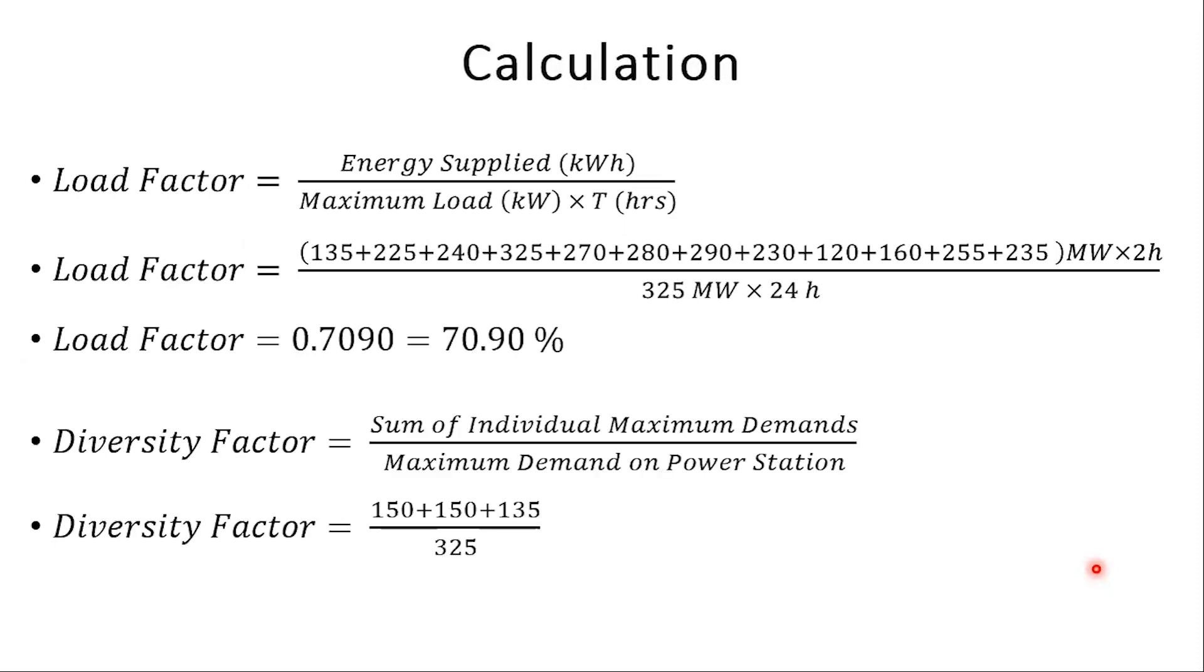Also, the individual maximum demands remain the same, but the time of occurrence is changed. We can conclude that as the load became more diverse, the load factor of the total load has increased.